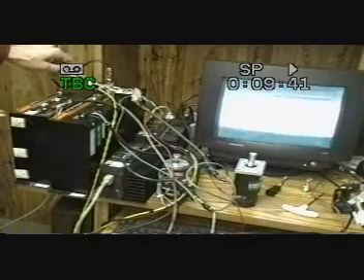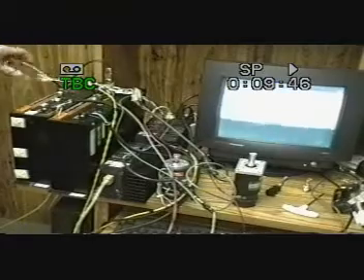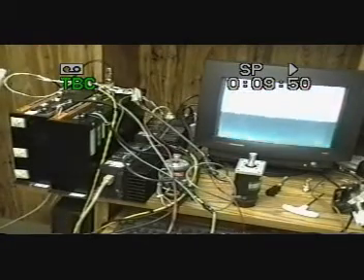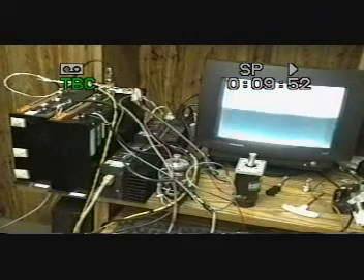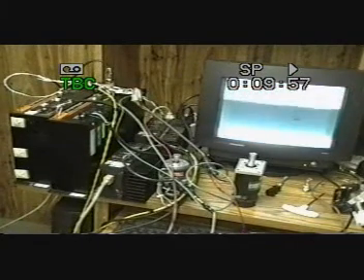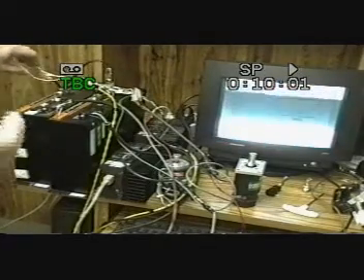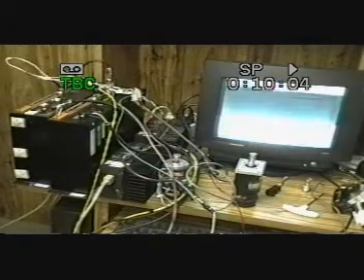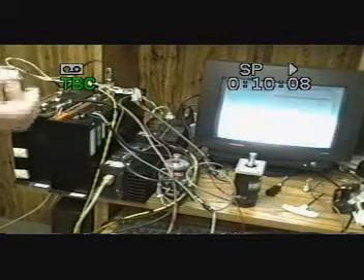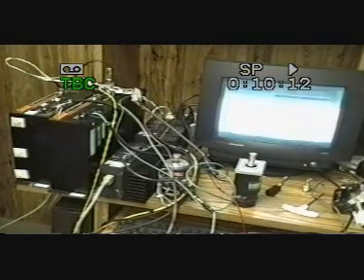This is a very low signal. It's 5 volts. It's very fast. Quadrature's coming in 4 times. The other thing that it could be is in your emulator, of course, the receiver drivers for those output pulses. I would check all groundings. Separate the encoder cables from any power cables, especially the motor cables or any high DC surge type currents, and clean off any contacts and make sure that all covers are closed.